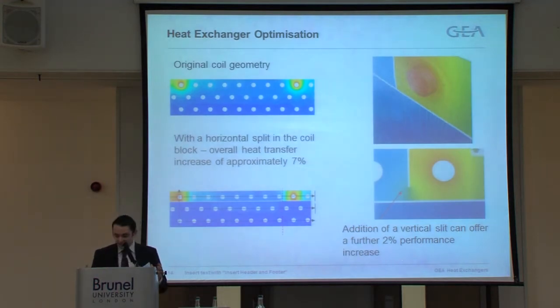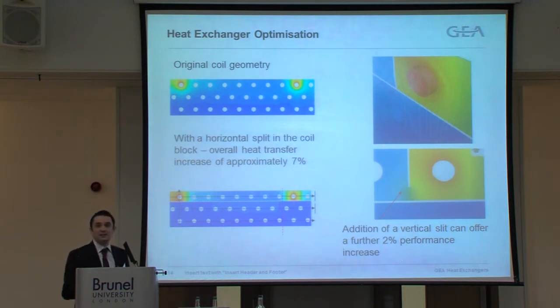Now, knowing that you get such significant temperature drop on the first few circuits of the coil, we could then use the CFD to try to optimize these coils. Those of you who are familiar with our gas cooler product already will be aware that we've got this horizontal split in there. We put that in there based upon our experience over the years working with steam coils and understanding that large temperature differences could pass some of that heat down to the tubes where you don't want it to be. What we didn't fully appreciate was the effect this was having on the capacity. We have now learned that it has a 7% performance effect on the capacity of the gas cooler, which can now be incorporated into our product, and you'll see that from the selections in the product selector.